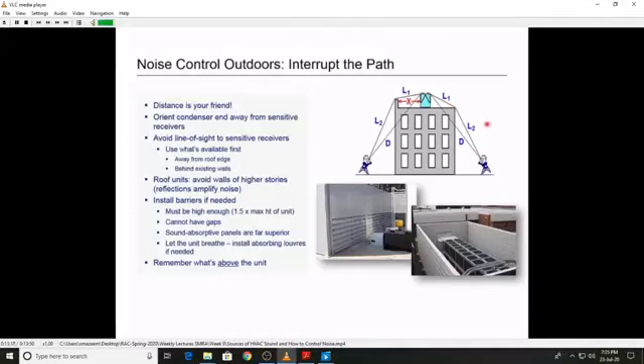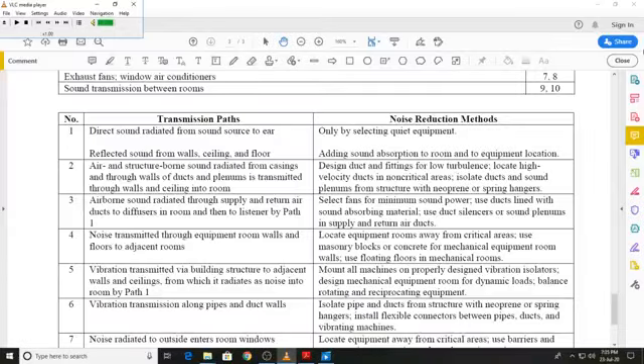If necessary, install barriers, but remember, they need to be high enough, they can't have gaps, and adding absorption or getting sound absorbing barrier panels can be a lot more effective. Finally, because it's HVAC equipment, you always need to be concerned about letting it breathe. So you may have to invest extra dollars in getting air breathing absorptive louvers to allow air to flow into the barriered space, but still have sound attenuation.